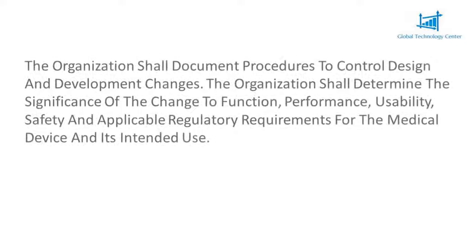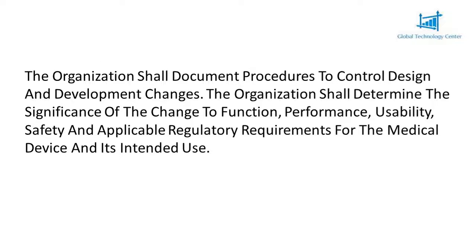Control of design changes. This clause talks about establishing procedures to control design changes. Use your procedures to control design changes. Maintain a record of medical device design changes. The organization shall document procedures to control design changes.